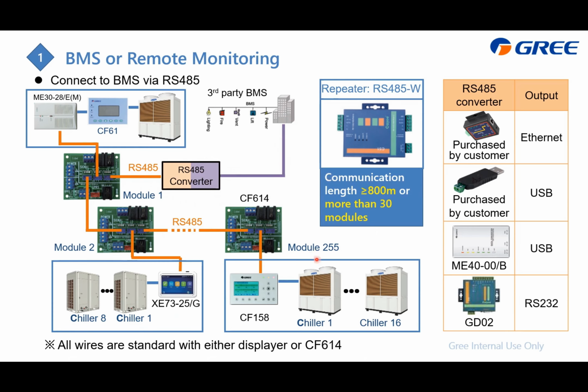If the communication length is more than 800 meters or there are more than 30 modules, you need to use this repeater to ensure the communication.